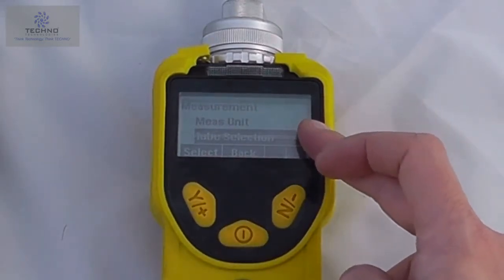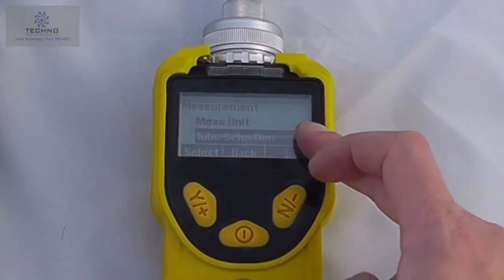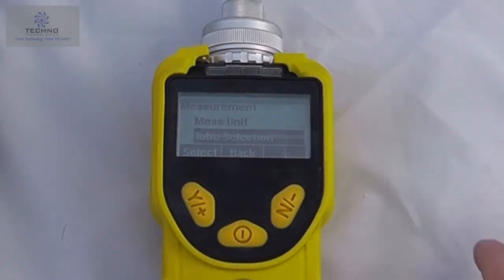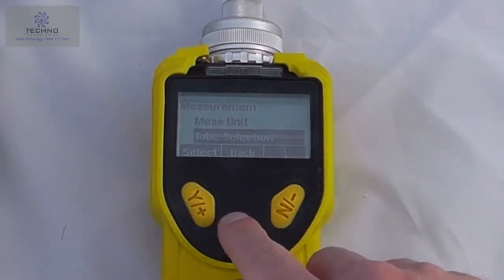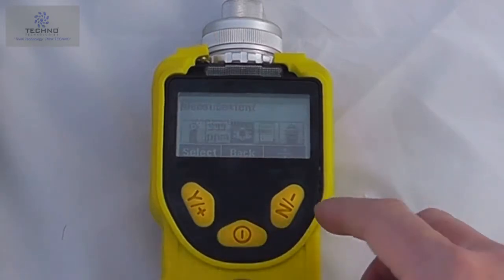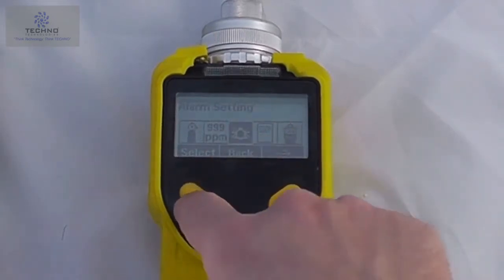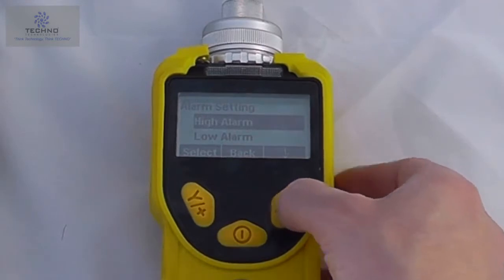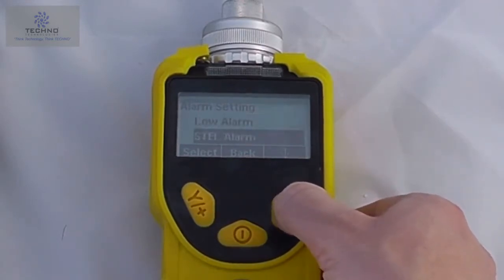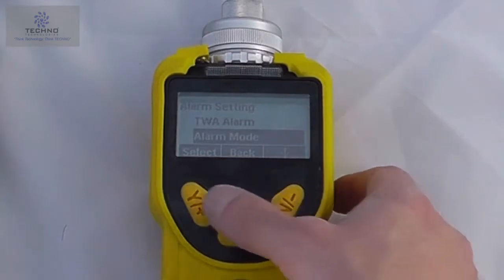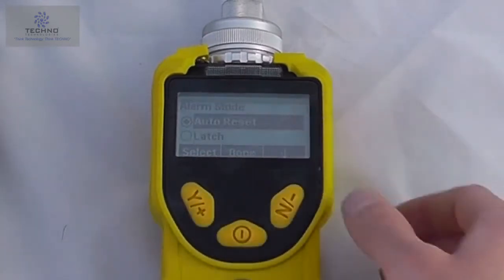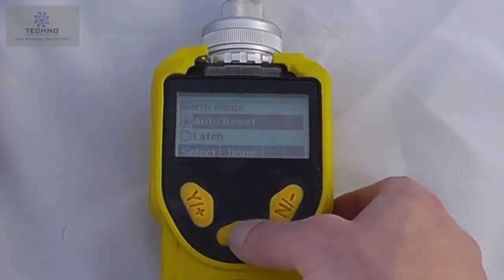Tube selection, this is only available, this is a firmware from the MiniRae 3000 instrument, which we'll look at in a bit more detail in a further video. So if I go into the alarm settings, I can look at things like my high alarm, I can change my low alarm settings, STEL alarm, TWA alarm, and our alarm mode. So be it an auto reset or a latching alarm.